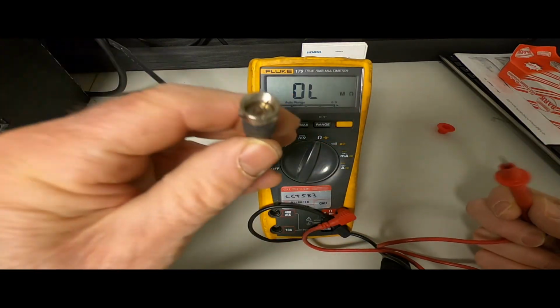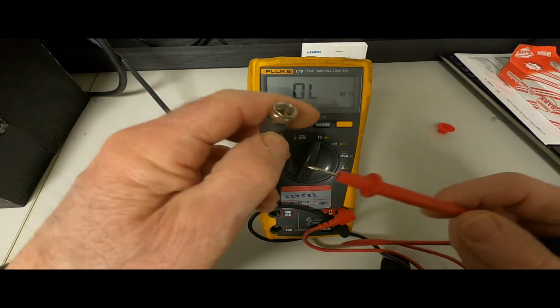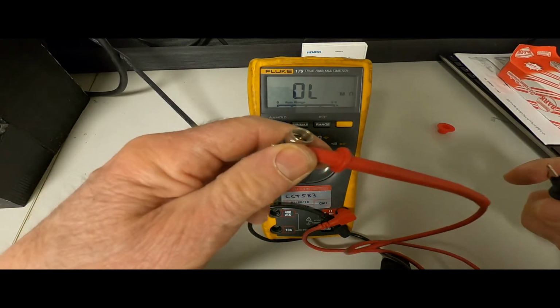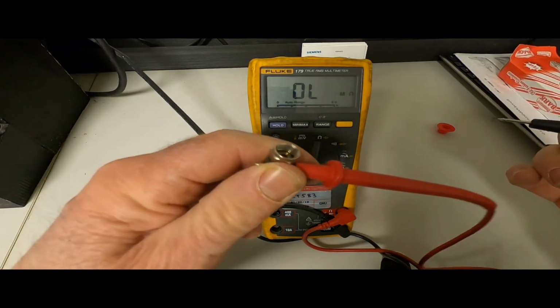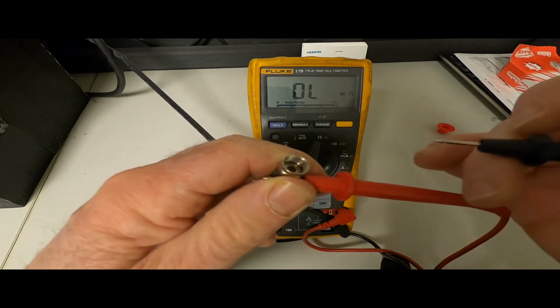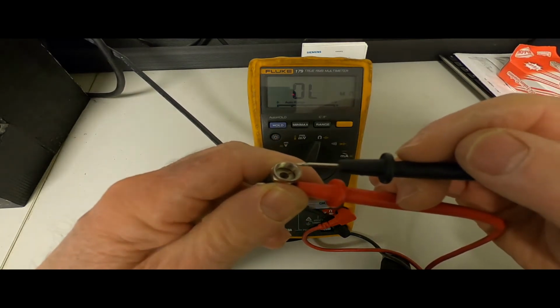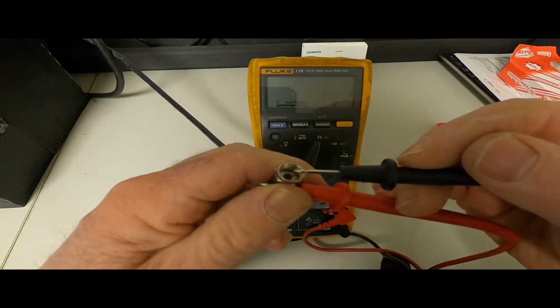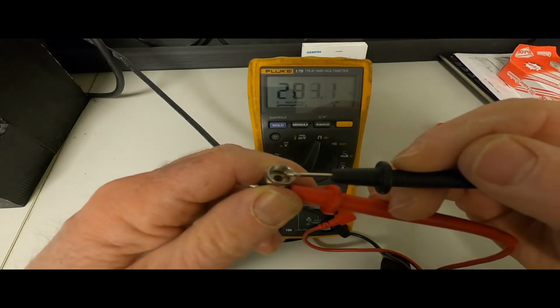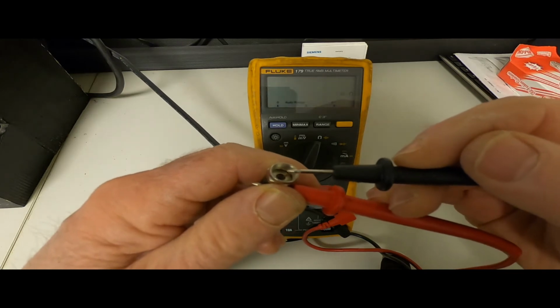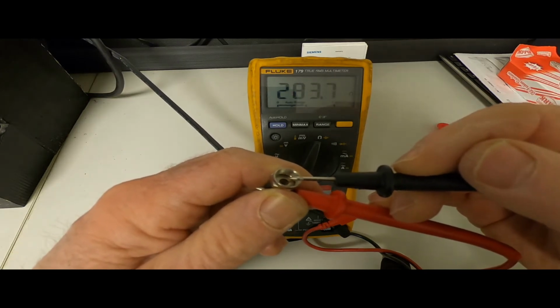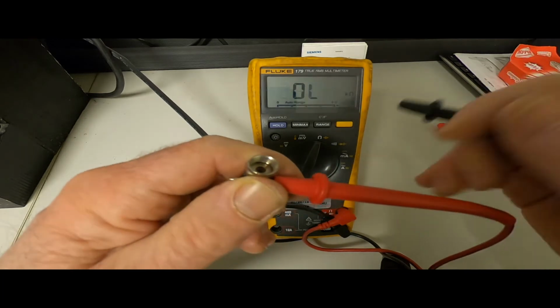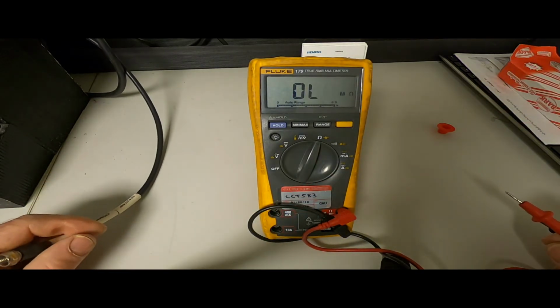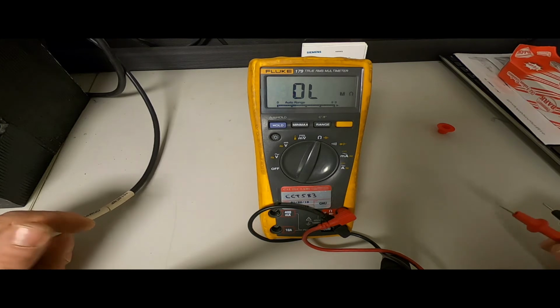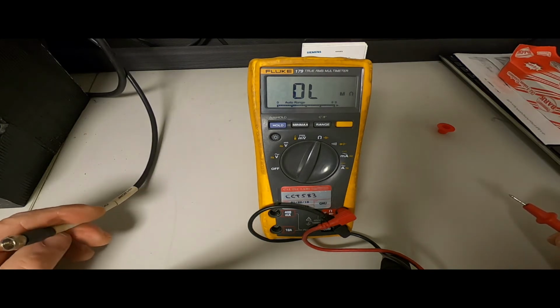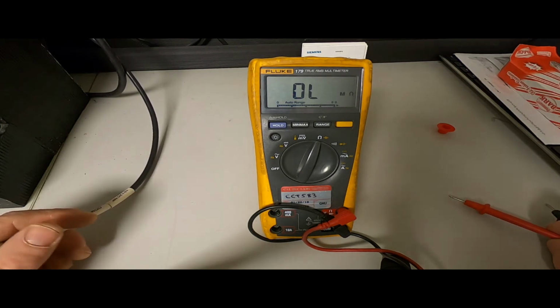Then take one of your flow sensor cables and simply take one probe from the ohm meter and hold it against the outside of the metal part of the F connector, and take the other probe and touch it to the center conductor, making sure that you're not shorting out the probe to the F connector, and you'll get a measurement. So in this case, I'm reading 283 ohms, and I'm actually checking a D1H transducer, a D1 high precision sensor, and that is the correct reading for that flow sensor.